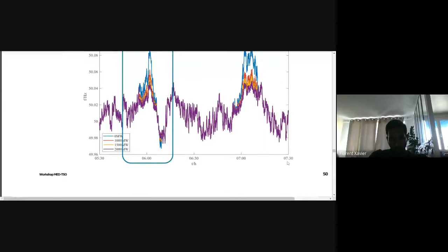In blue, we have the system without batteries and without regulation. The orange is 1,000 megawatts, in yellow 1,500, and the most powerful is 2,000 megawatts. So you can see that if you put a control on our system with batteries, we can reduce the impact of deterministic frequency deviation. It seems easier, but today for classical generation units or renewable energy, it's very difficult to participate in a system very quickly. So that's an example that I showed of the utility of batteries.